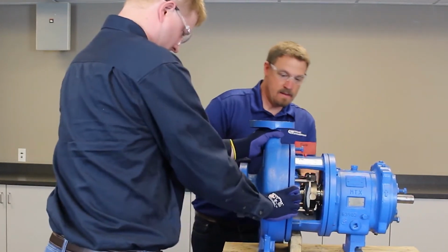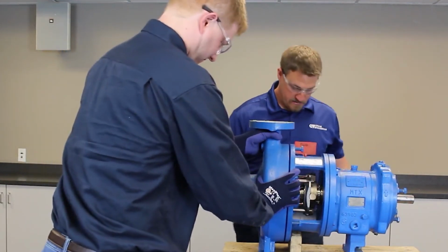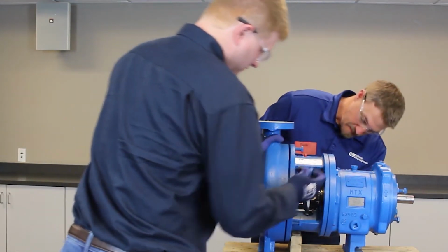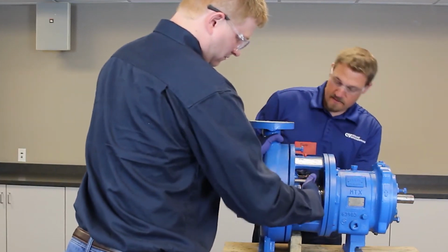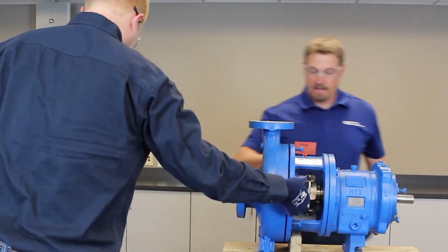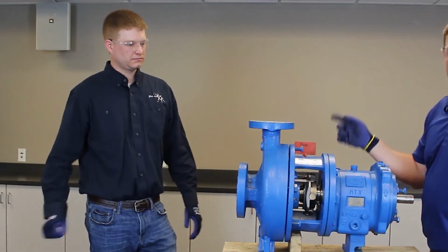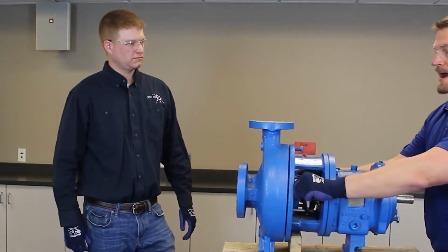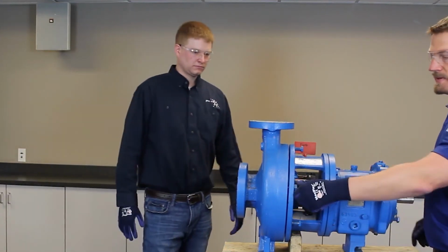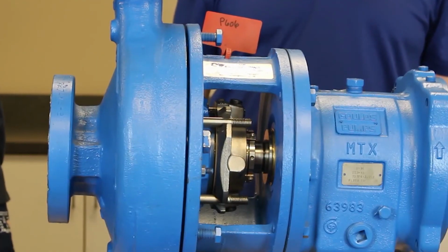Okay. Slide that up tight. And now we're ready to put in the bolts. Okay, and when you are tightening the casing, just like everything else we've talked about, you're going to want to go basically finger tight. You're going to want to work your way around, alternating pattern, 180-degree pattern, and then just quarter turns, just like you do when you're tightening the lug nuts on your vehicle.